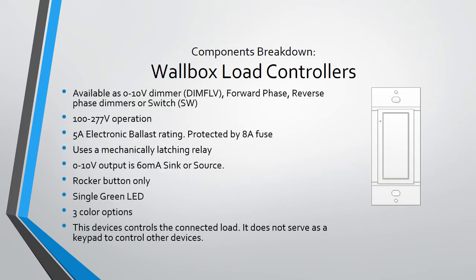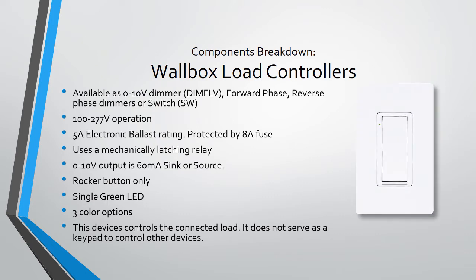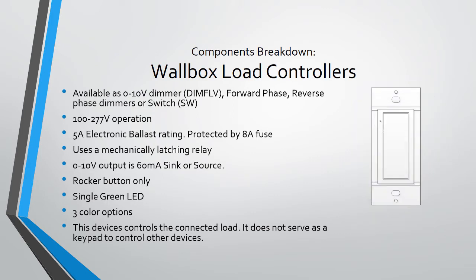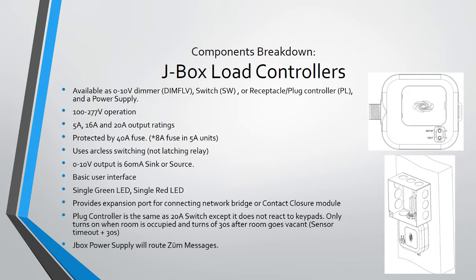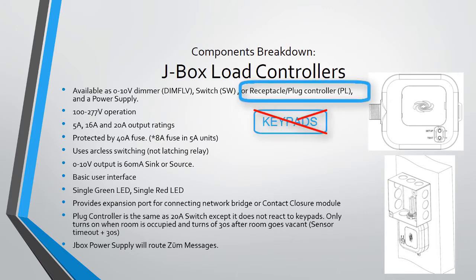Now on to some specs of each Zum device. Wall boxes come in a few flavors — aesthetically they look like the regular Crestron C2W dimmers or switches. All wall boxes operate on 100 to 277 volts, protected by an 8-amp fuse. The 0-to-10V can both source or sink up to 60 milliamps. Dimmers and switches are only available as a rocker button layout in three standard color options. Keep in mind that switches or dimmers do not serve as a keypad to control other devices — each device controls itself. J-box load controllers are mounted directly to a junction box, typically behind drop ceilings. These control one or more sets of loads and come in 0-to-10V dimmer, switching operation, and receptacle control. They use arc-less switching. The plug load controller does not react to keypads; it turns on based only on occupancy information.